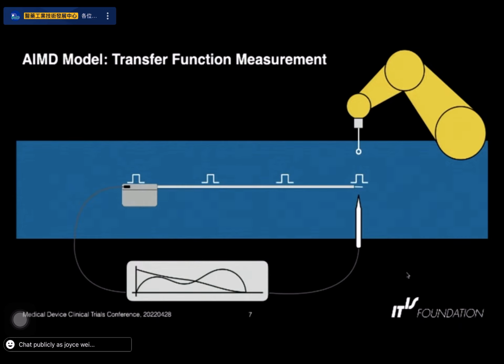So this is how a model of the device is created. I go through this very quickly just to give you the background on what these inputs would be. So we take a device and we apply piecewise fields along the length of the device at 64 megahertz, and we measure the response either of the tip, which is in contact with the tissue, the E fields around the tip, or with the voltage in the can.